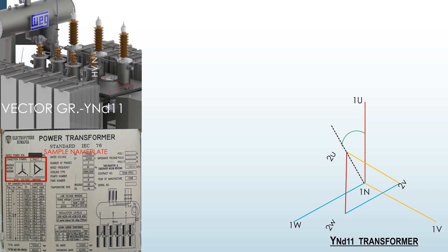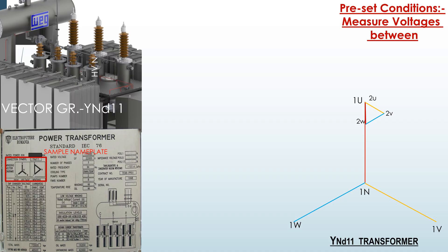And a 30 degree phase shift with secondary voltage leading the primary voltage. After connecting the HV neutral to ground and joining 1U of HV winding to 2U of LV winding, voltages to be measured between specific points according to predefined conditions for satisfying the relations of YND11. Watch the vector group diagram and conditions.